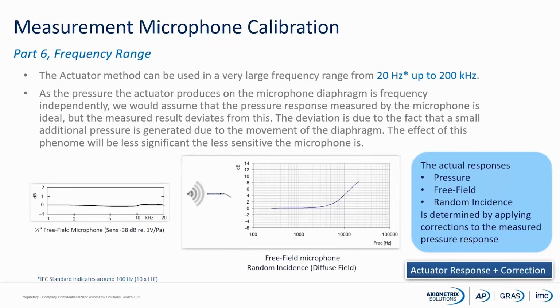So normally you will consider the obtained level as the pressure level the microphone has measured. So the actuator will give us a pressure measurement, and it means that, of course, when we are measuring free-field microphones as well as random incidence microphones, we have to do a compensation to find out how the microphone will act in a really free-field environment or a really random incidence environment. So we have to add the free-field and random incidence or diffuse field corrections to our pressure measurements.